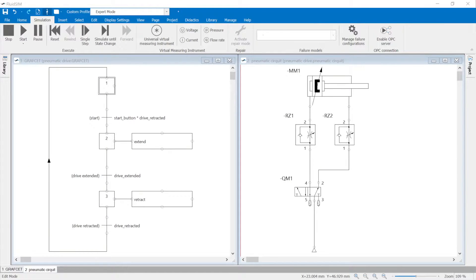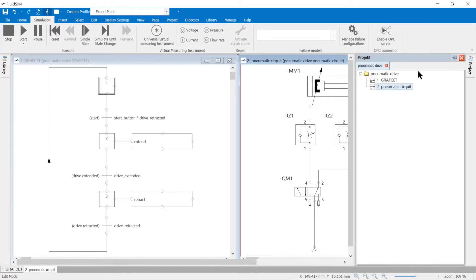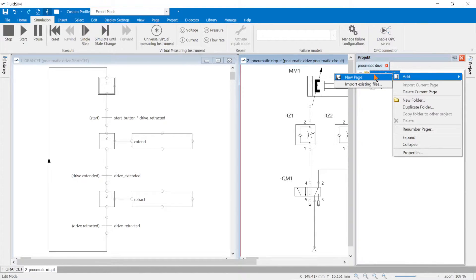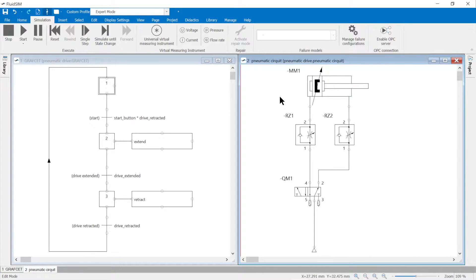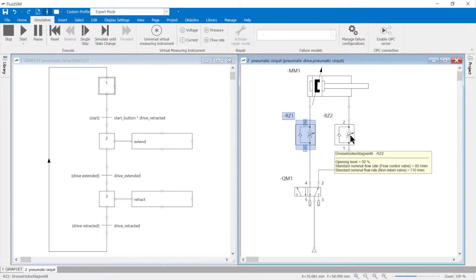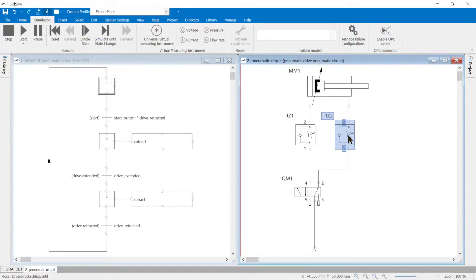To develop a pneumatic circuit diagram from the GRAFCET, a new sheet is inserted in the project on which the pneumatic circuit diagram will be developed. A double-acting working cylinder is connected to a configurable 5/N-way valve. Two one-way flow control valves are added for supply airflow control to adjust the speed. Port one of the 5/N-way valve is connected to a compressed air source.